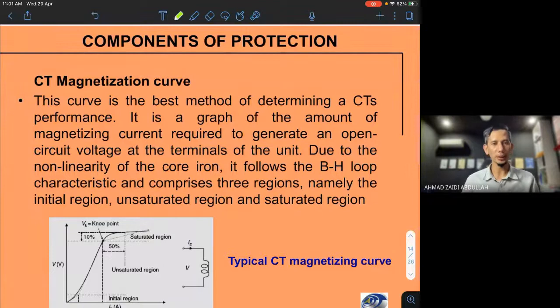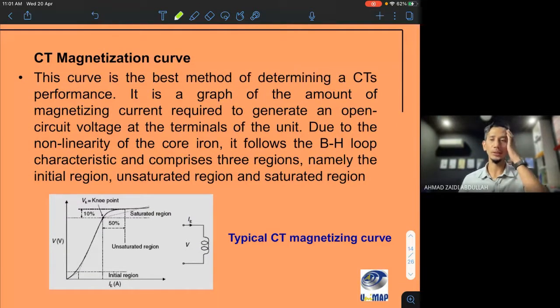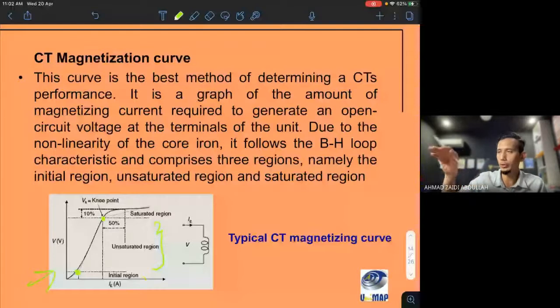And then this is the CT magnetizing curve, which you also need to understand to know how the current transformer works. Referring to this figure, this curve we call the magnetizing curve. Normally we use this region only for the current transformer, because the first part is the initial region. And then we also have the knee point for all CTs. Normally, when we want to buy, they tell us the value of the knee point. We call it the knee point. And after the knee point there is the saturated region.